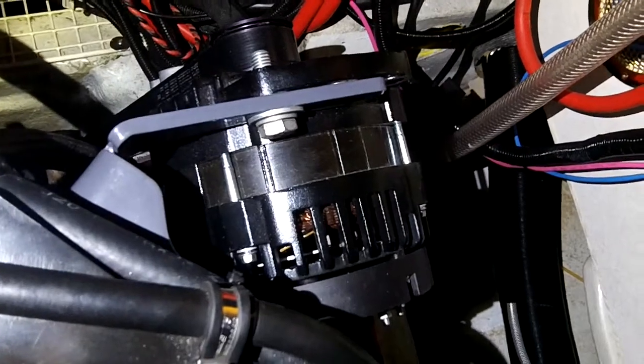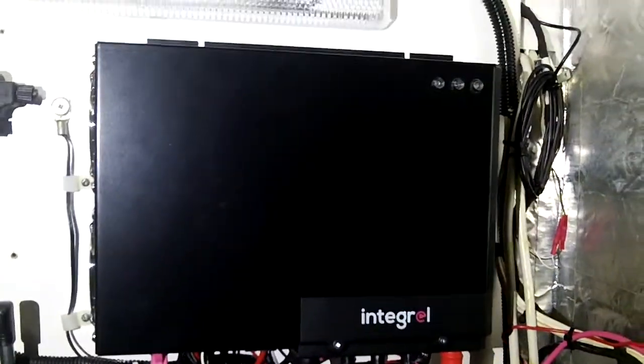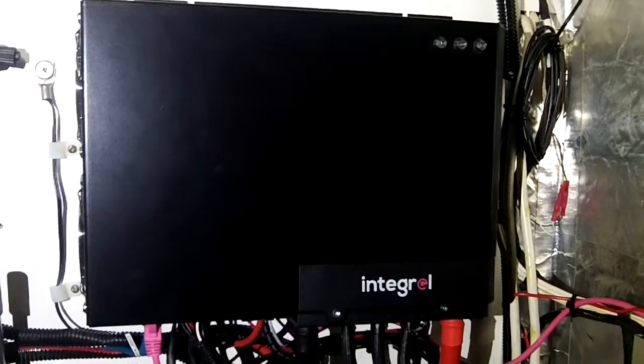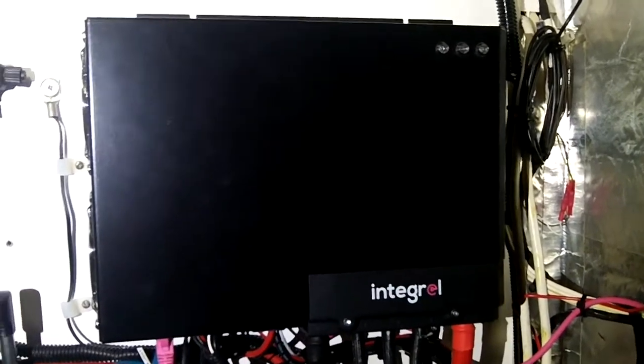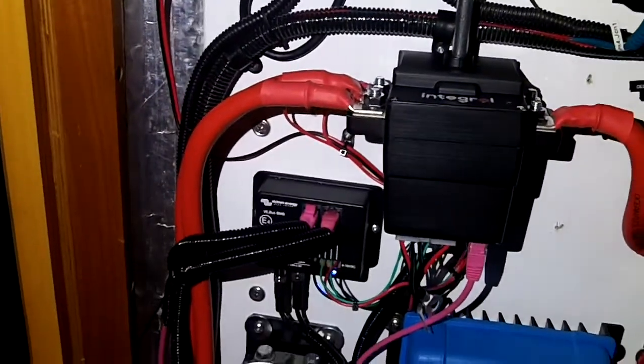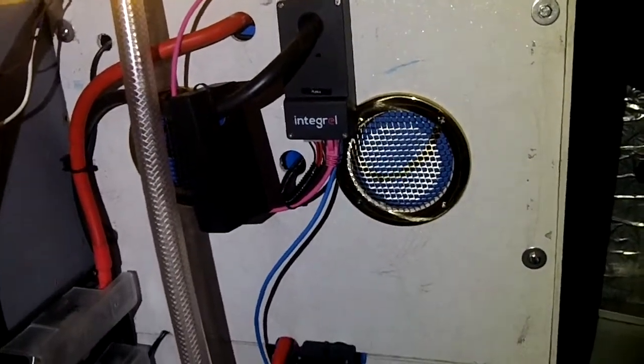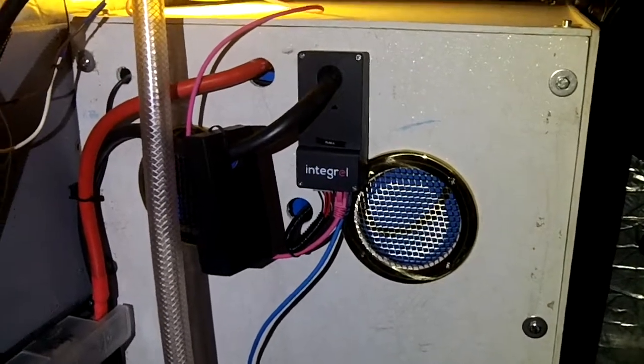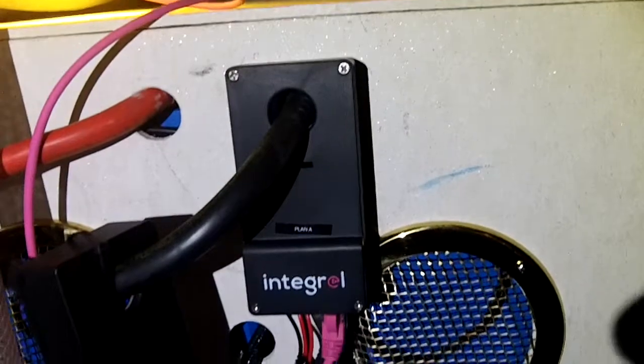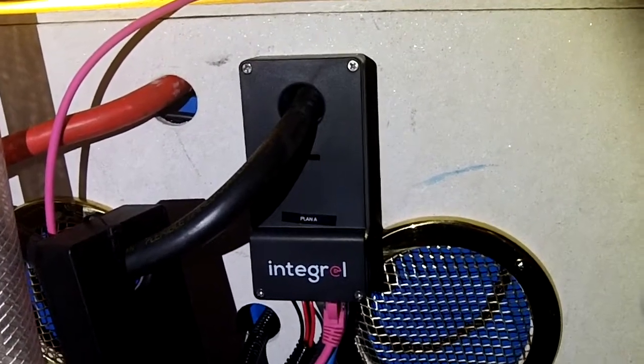The generator produces variable frequency, variable voltage electrical output, which goes to the controller, which you can see here. That converts it into a very stable 48V DC output. From there it goes through the red wire via the switch, and across to the battery bank. Behind those white panels is 20kWh of Victron lithium-ion batteries, and each one is monitored by this little device on the front, which is the battery management system for Integrel.